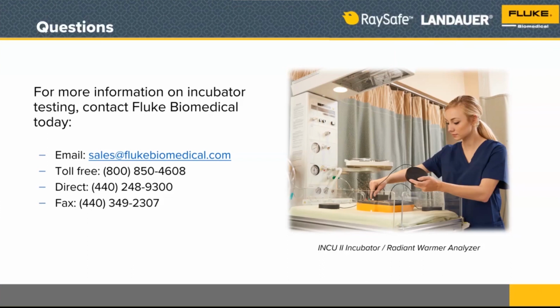Manufacturers like Fluke have an uncertainty requirement. How certain are we that a calibration of the test instrument will hold for the period of time we specify as the calibration life? Right now we believe our test instruments need to be recalibrated every year, because we are absolutely certain they should stay within specifications for that duration. Beyond that time, there's more uncertainty about whether your measurement is still within the tolerance bands for cal.